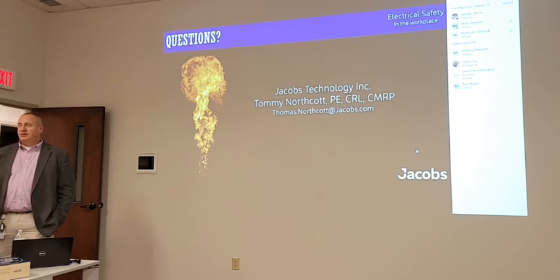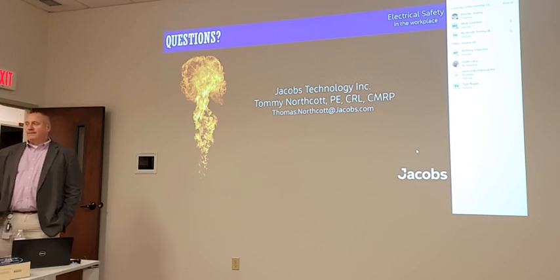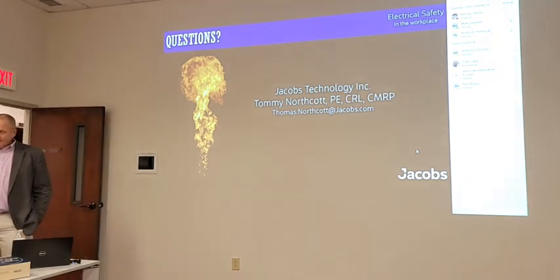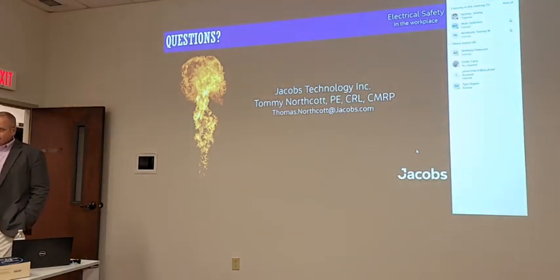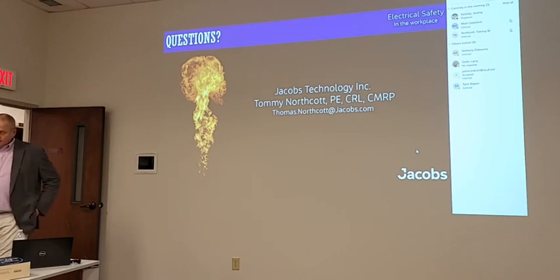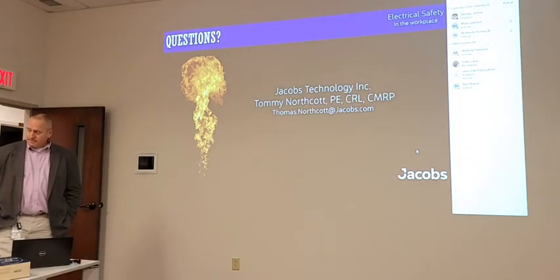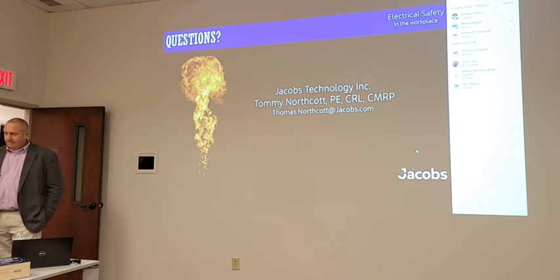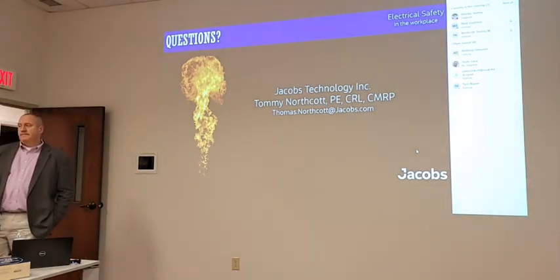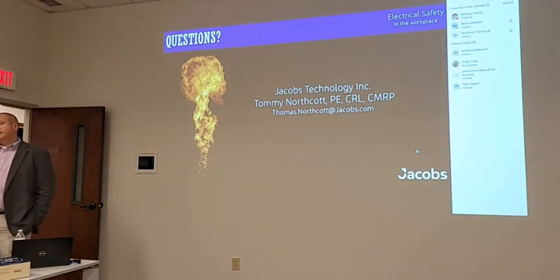Next question, I don't know if Kabir gets asked to do this, but I was talking with one integrator, and he said that customers are starting to ask them to do the arc flash calculations. And to do that, correct me if I'm wrong, does that integrator need access to the entire model? Because they say, we're going to feed that with this breaker here, and there's this many amps available with short circuit current, you've got to run this thing 40 feet, 50 feet, or whatever. You figure out with that short circuit current what the available current is at this point here, what the clearing time of that breaker might be.